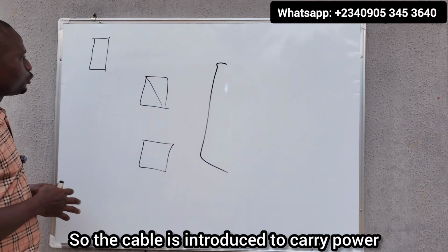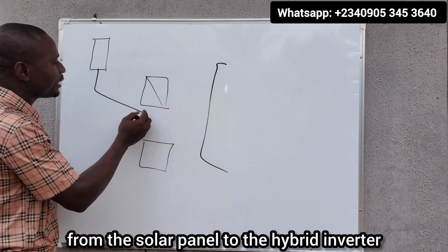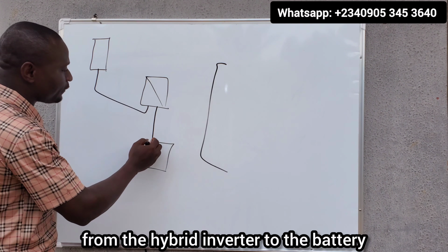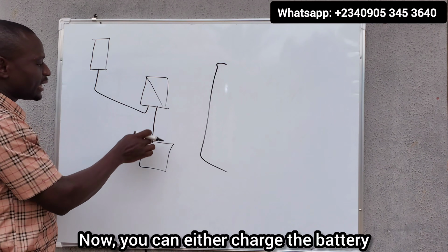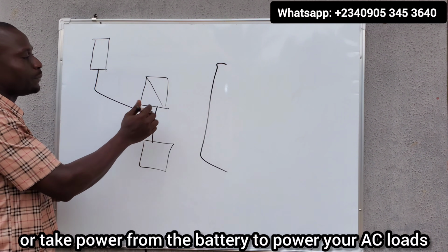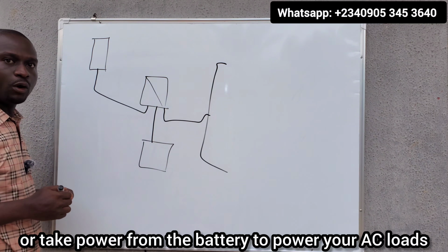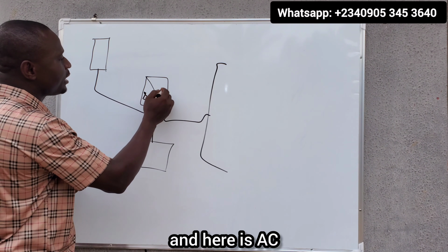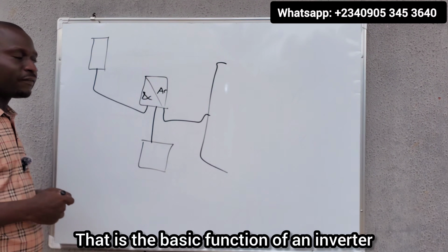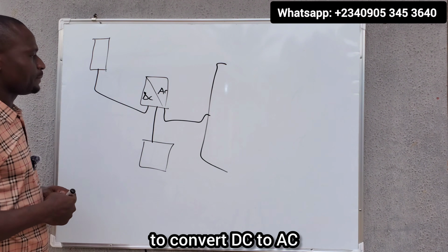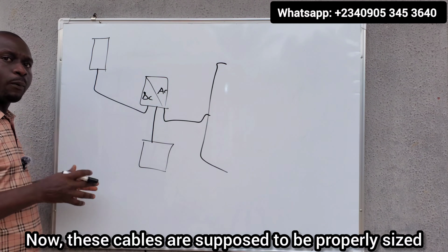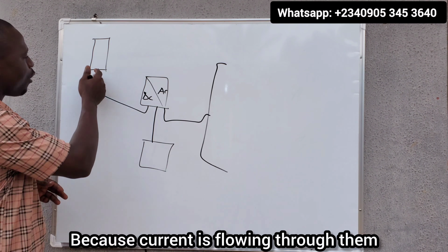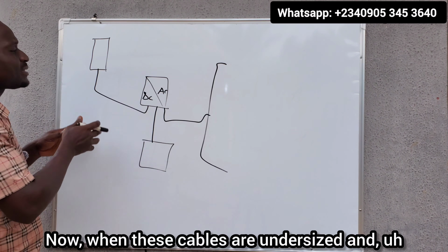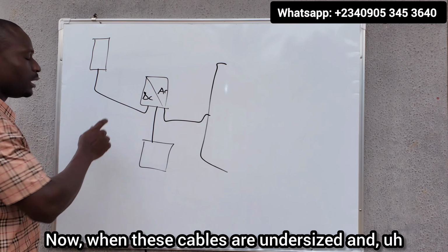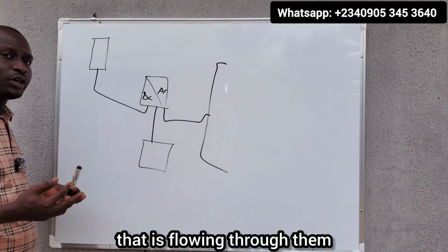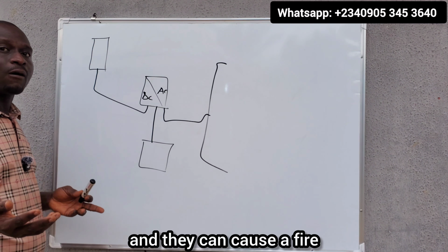So the cable is introduced to carry power from the solar panel to the hybrid inverter, from the hybrid inverter to the battery. Now, you can either charge the battery or take power from the battery to power your AC loads, because here is DC and here is AC. That is the basic function of an inverter, to convert DC to AC. Now, these cables are supposed to be properly sized. Why? Because current is flowing through them. Now, when these cables are undersized and they cannot carry the amount of current that is flowing through them, these cables will overheat and they can cause a fire.